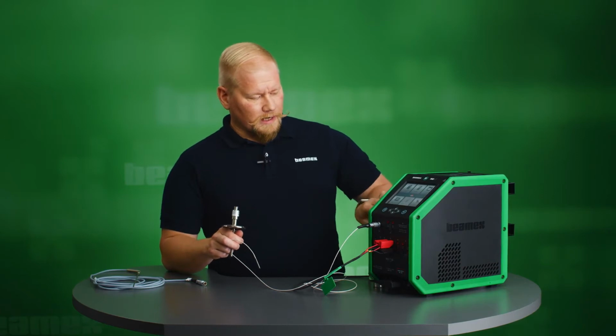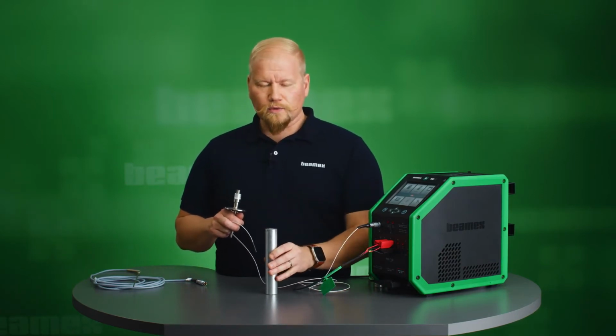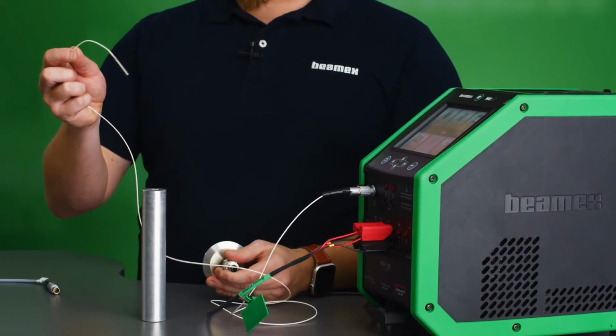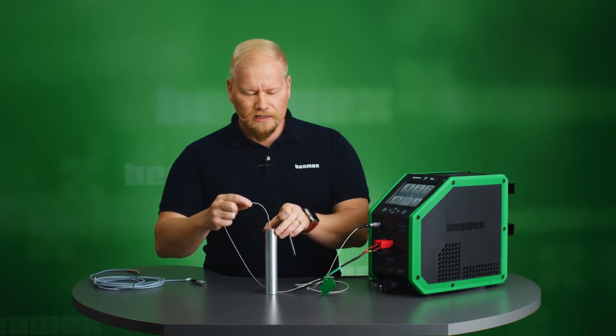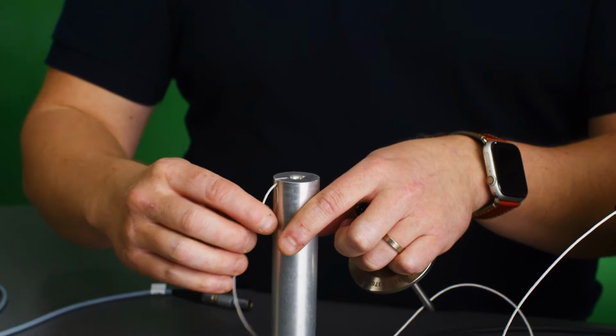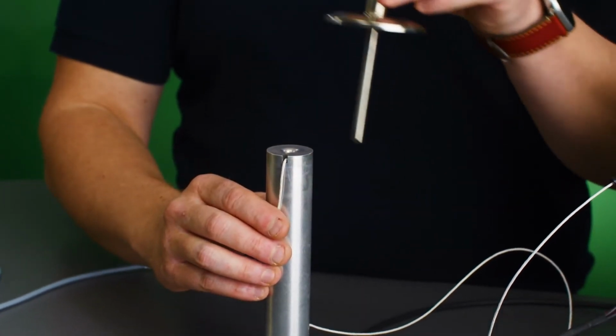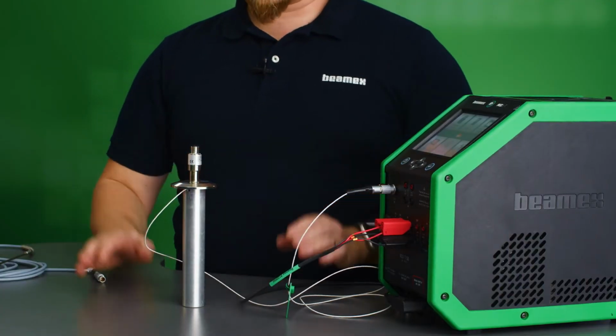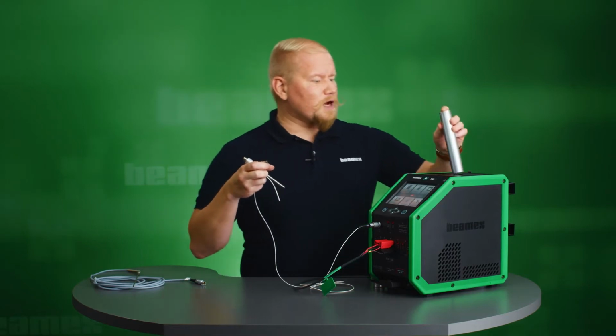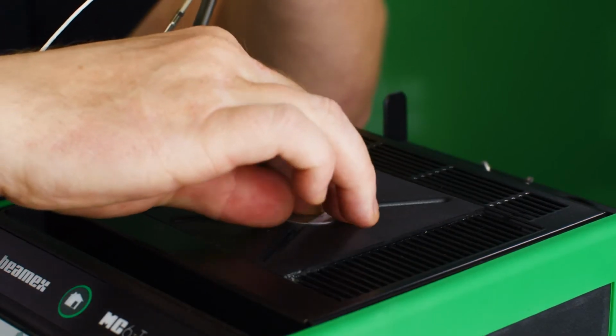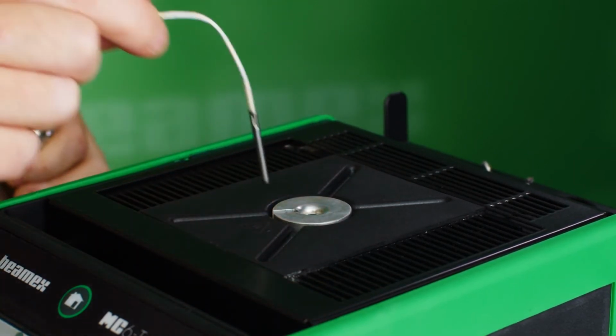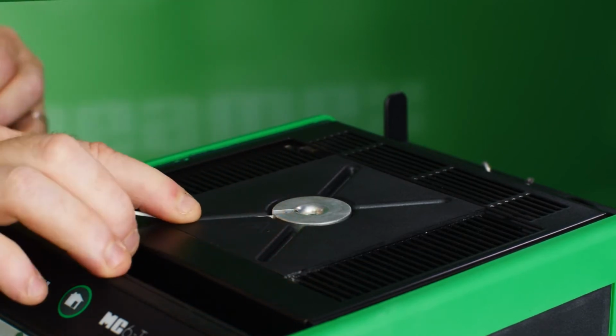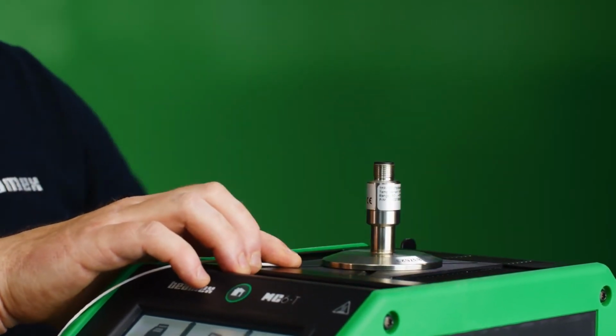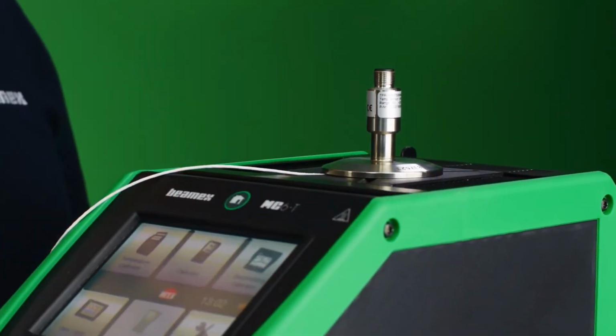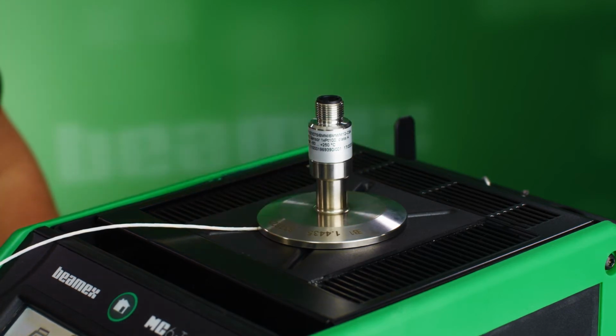To solve this, I have a specially made insert with 2 holes, one for the instrument and one for the reference, and the holes go to the same depth. So now when I place the reference here, it stops where it should. There's also a groove so the cable can come out on the side. And now when I place my instrument into the hole, I get a fully flush surface. When I move this to my dry block, there are also grooves on top of the dry block, which help me get the cable out from the insert. So now when I place my sensor on top, I get a fully flush surface. This helps with the heat conduction. I know I'm going to get good, consistent results with small uncertainties.